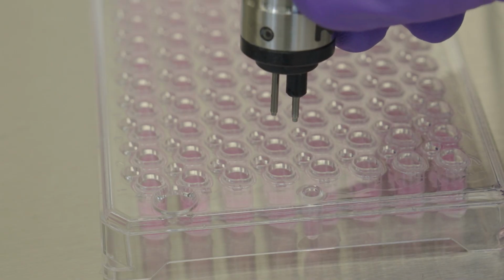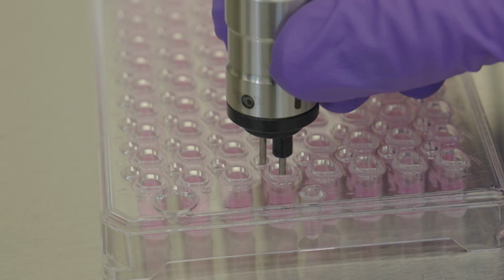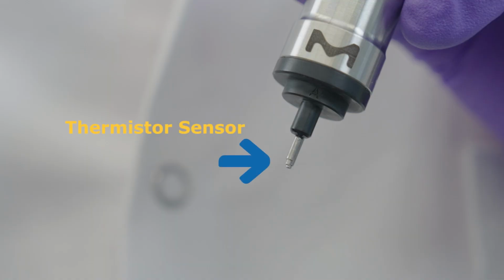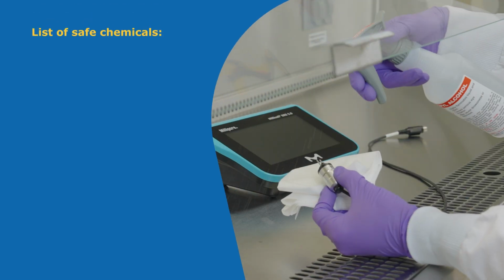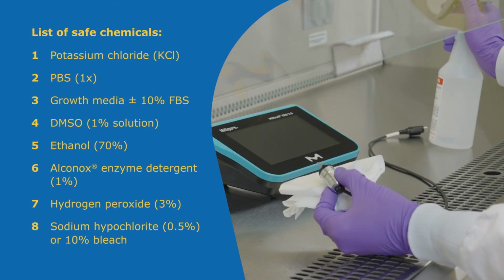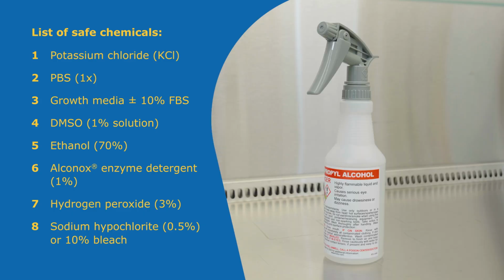This probe leg is placed into the receiver plate port. The thermistor is located inside the tip of the apical probe leg to measure temperature of the cells in culture more accurately. It is recommended to clean the probe with 70% ethanol. Shorter 10% bleach cleanings are also okay.